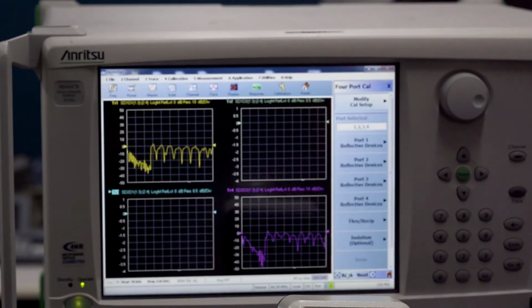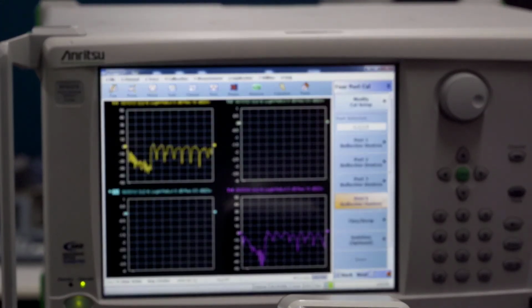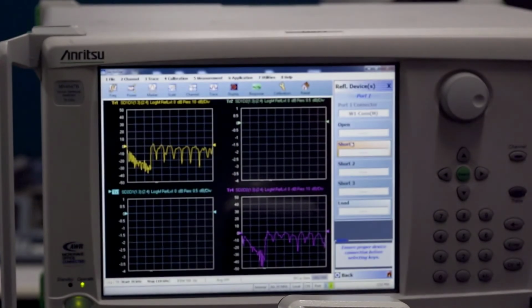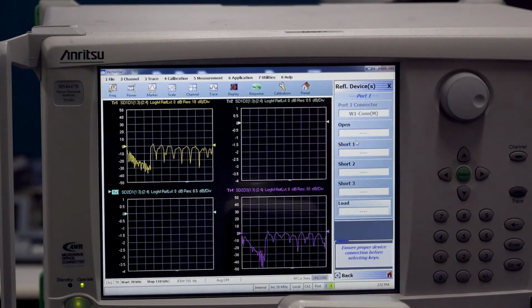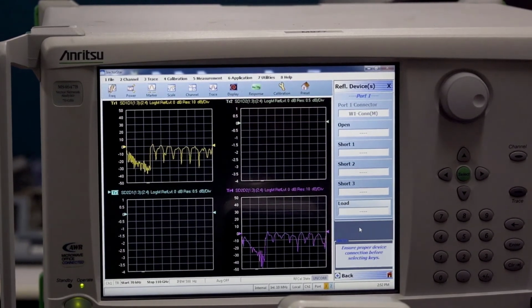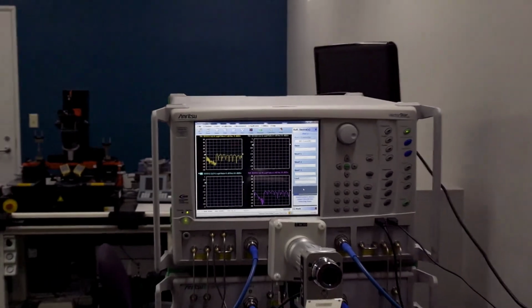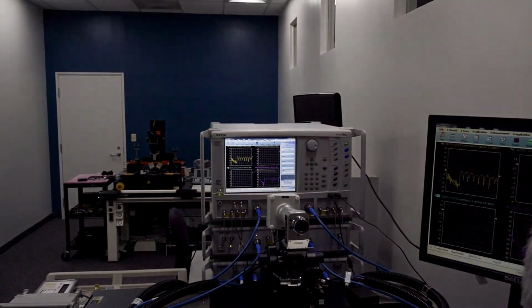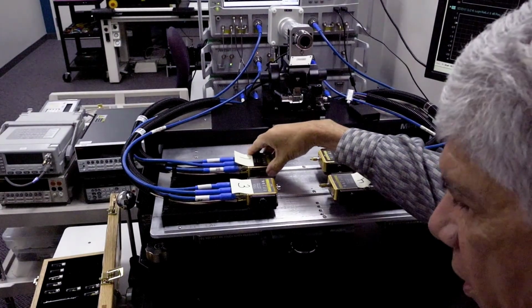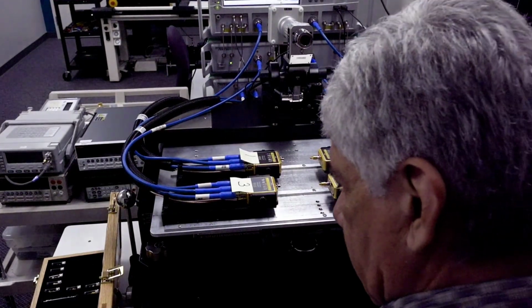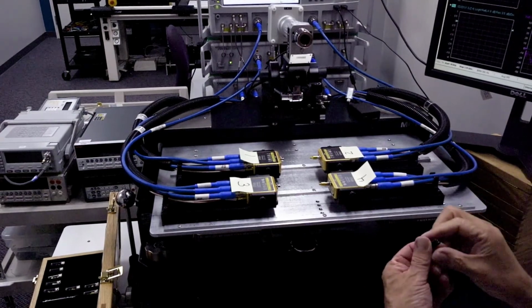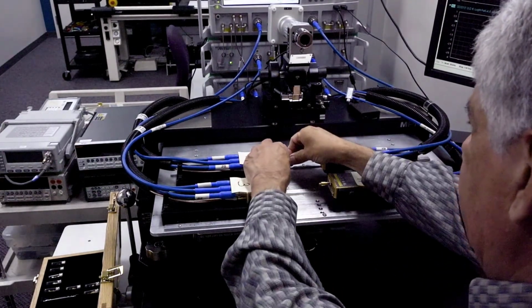set up for our calibration, and we go to port 1 to start off with, and you see that we have requirements for our reflective devices, the open, shorts, and the loads. And so now we will start to add those standards to our test port in order to do our calibration. For port 1, we need an open connected.